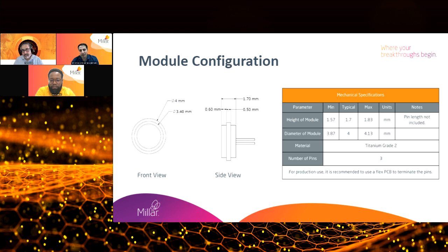The TiSense is made with a technology that makes it quite robust. This technology is used for space applications or submarine applications, which confirms the robustness of the device in very harsh environments. And in case there is any tear in the device that leads to leakage of the silicone oil, which is quite rare, silicone oil is an inert material, and it is well known that it doesn't do any harm to the human body.